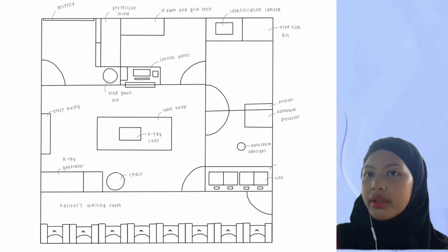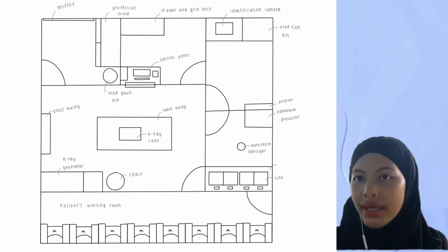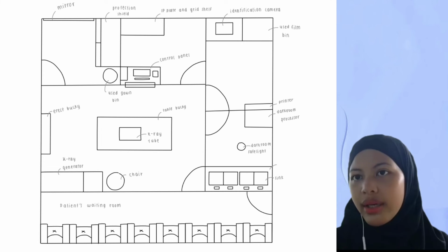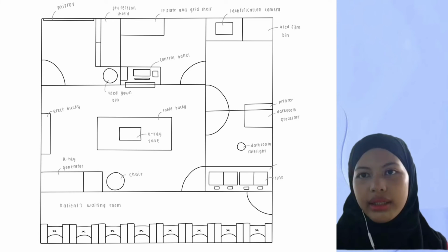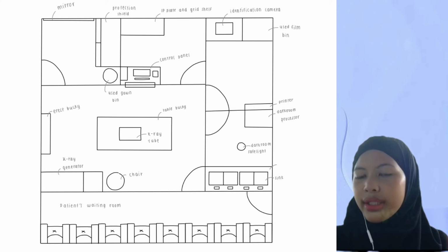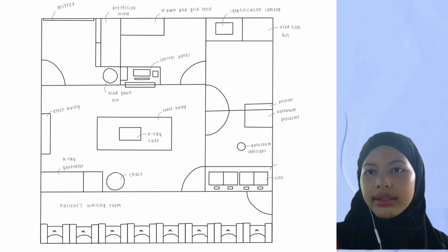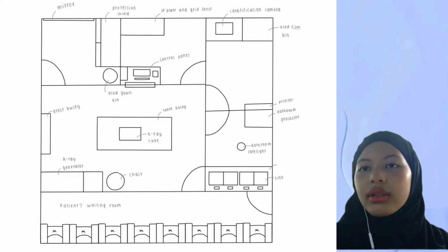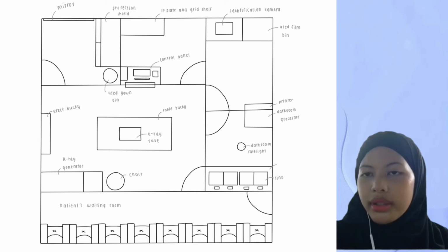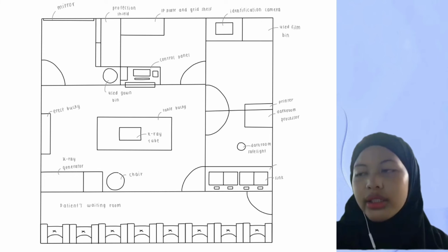Next, the control panel must be placed at the other side of the X-ray room. It must not be placed at the patient's waiting room. This is very important. Why? Because the control panel cannot be at the place where it's reachable for the patients in order for the patients to not mess around with the X-ray instrument. Mostly the control panel itself. In addition, in the control panel, there is the button used to expose the patient.